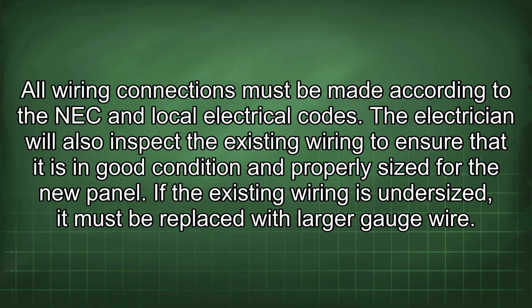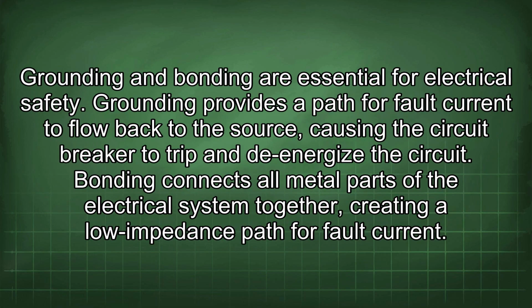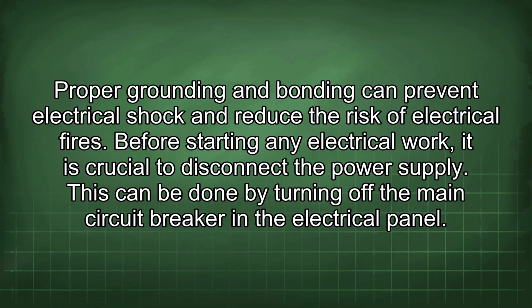The electrician will also inspect the existing wiring to ensure that it is in good condition and properly sized for the new panel. If the existing wiring is undersized, it must be replaced with larger gauge wire. Grounding and bonding are essential for electrical safety. Grounding provides a path for fault current to flow back to the source, causing the circuit breaker to trip and de-energize the circuit. Bonding connects all metal parts of the electrical system together, creating a low impedance path for fault current. Proper grounding and bonding can prevent electrical shock and reduce the risk of electrical fires.